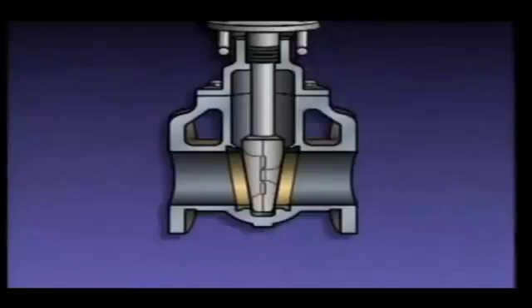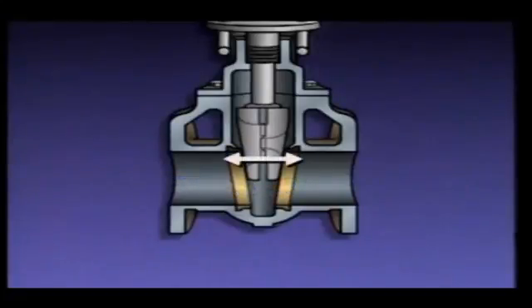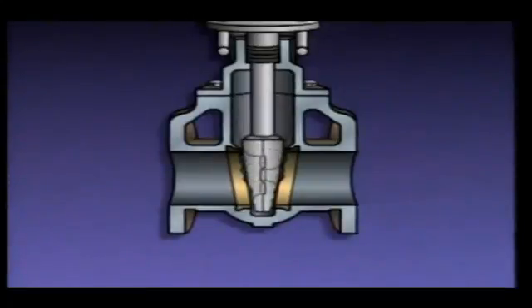Gate valves are normally used in on-off applications, but in an emergency they can be used to throttle flow. However, long-term use as a throttling valve can damage a gate valve. In many types of gate valves, when the disc is raised slightly, fluid flow through the valve creates turbulence, which causes the disc to swing from side to side, banging or chattering against the seat. This chattering will cause wear on the seat and disc, and eventually the valve will not shut off flow when it's completely closed.